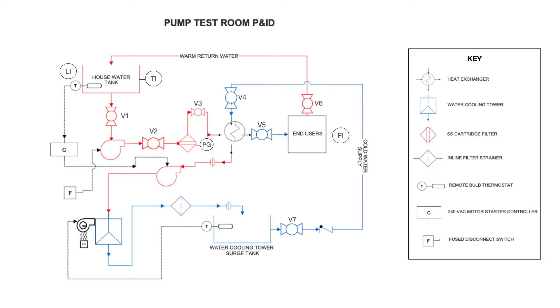The water cooling tower surge tank on the bottom of the screen has cold water in it, goes through a ball valve which is labeled as V7, then goes through a one-way check valve. The cold water supply then travels through yet another ball valve, valve 4, into the heat exchanger.